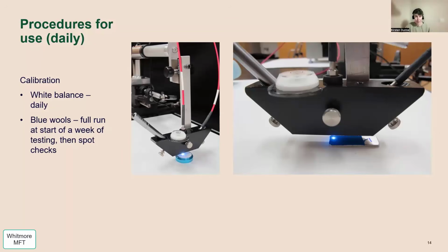This setup uses a manual focus, which I'm quite happy with. It's a case of just moving that measuring head up and down using a turn knob on the side to get the maximum reflectance from your test site. I currently also have a manual shutter to start and end test runs, but I believe on the LED setup, you can have a switch on the lamp so you can operate that remotely.